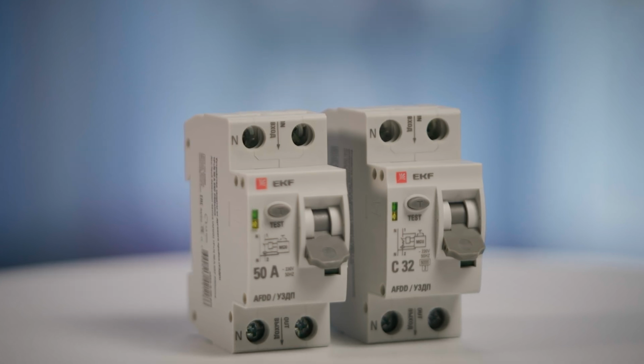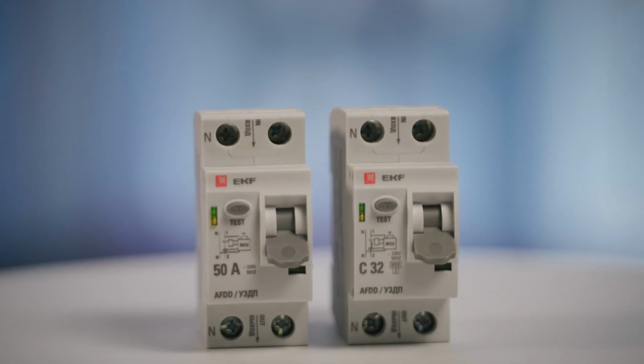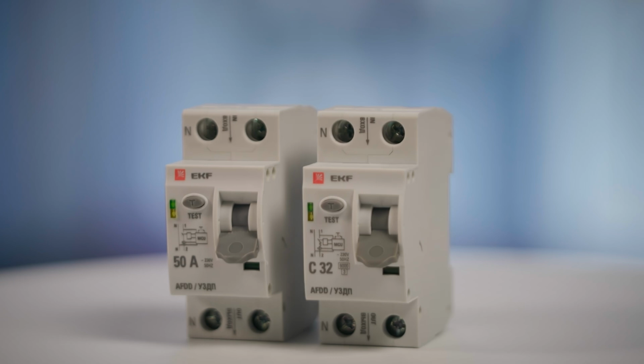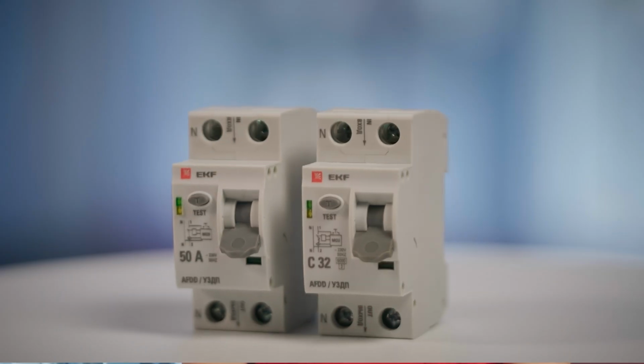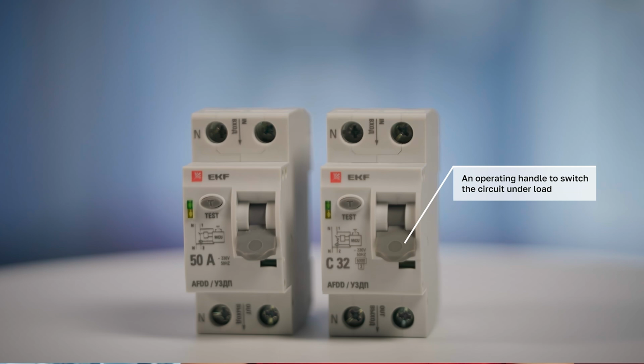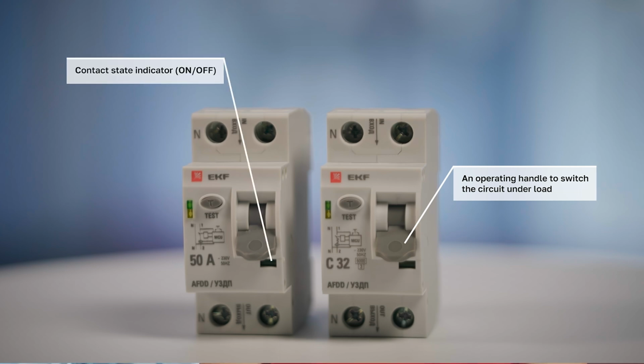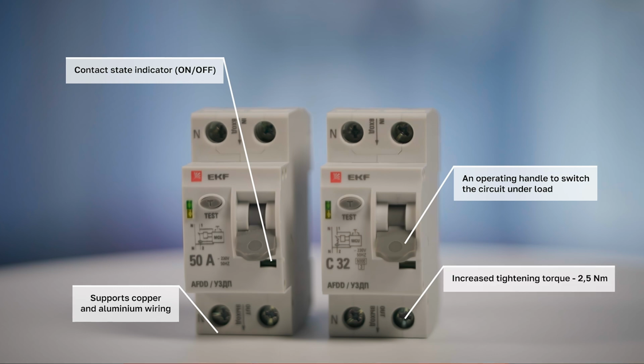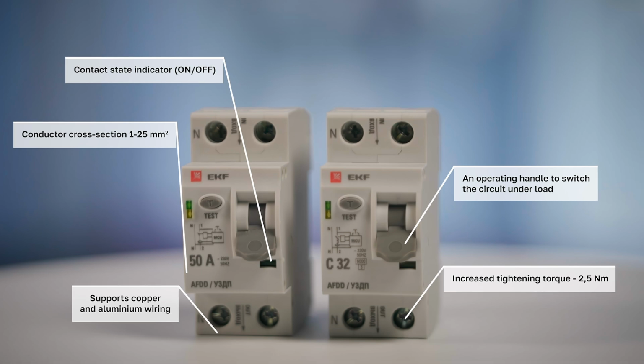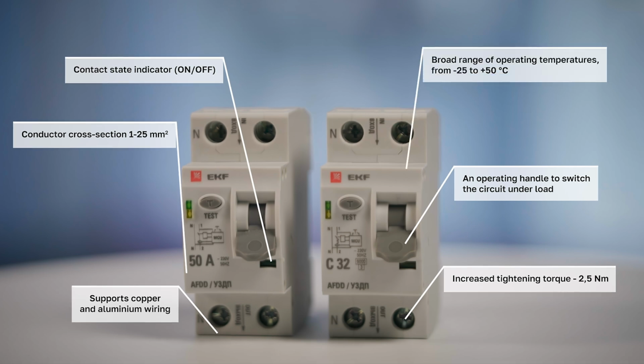A green LED to confirm that the AFDD is operating as intended. A yellow LED to indicate an arc fault. So the green LED indicates proper operation of the AFDD, and the yellow LED shows that the device has been triggered by an arc fault. An operating handle to switch the circuit under load. Contact state indicator that shows red if the device is on or green if it's off. Wiring can be done using copper and aluminum conductors. Increased tightening torque of 2.5 Nm. Cross-section of connected conductors from 1 to 25 square millimeters. Broad range of operating temperatures from -25 to +50 degrees Celsius.